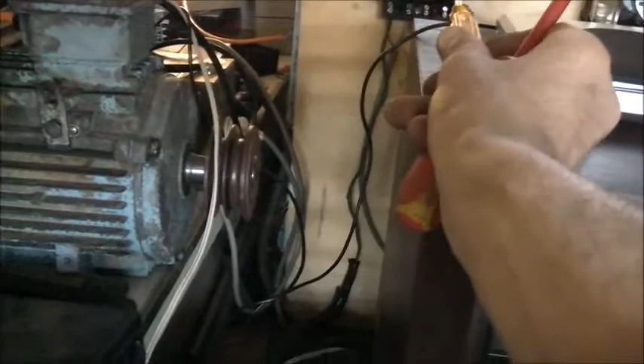So what you do, you unscrew your active, neutral, and I think your load. Yeah, neutral, active, and your load have to undo. So your neutral, active, and your load, and you place those screws with these connectors. And that's done with this screwdriver. They screw into the terminal screw holes of those terminal blocks of those meters.